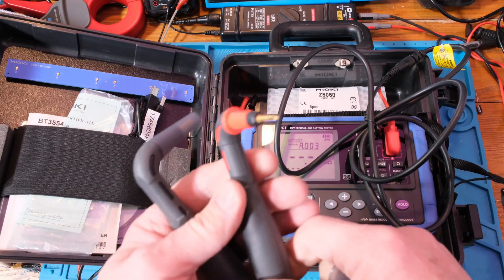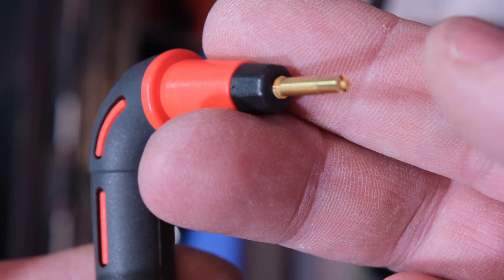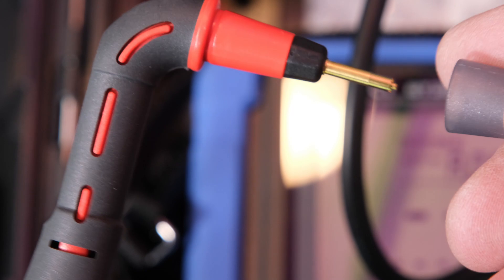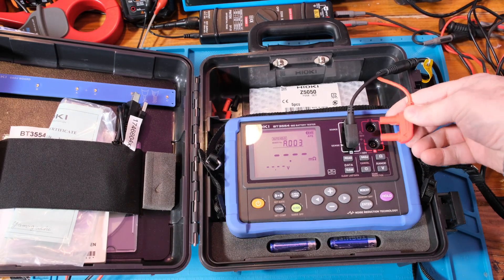Let me show you the lead while we're looking at this thing. So that's what it looks like — it's a little springy thing here when you push on it. It knows when you make contact. Just a nice tip in there. That's how this thing gives such great measurements. The black tip is just like it. One thing about it is you can see it has both the sense and the measurement — you have the source and the sense on both plus and minus together.